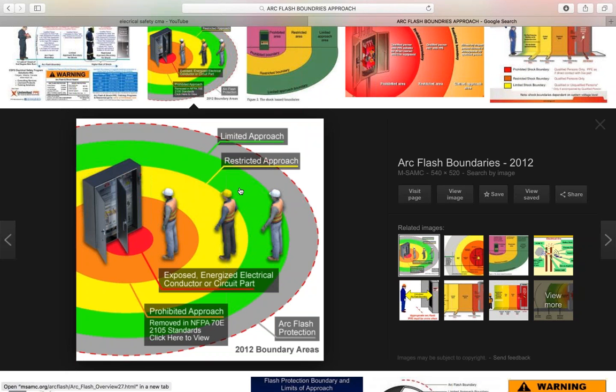Now let me tell you, folks, if you go back to page two again one more time. We're least probable to have arc flash hazards under 240 volts. Normally they're rarely possible within 240, almost never possible at 120 because it's a lower voltage. But normally anything over 240, and then we get into the 400s, the 600s, into the thousands, that's where we start accepting a significant risk that there may be an arc flash. All right, great, folks.